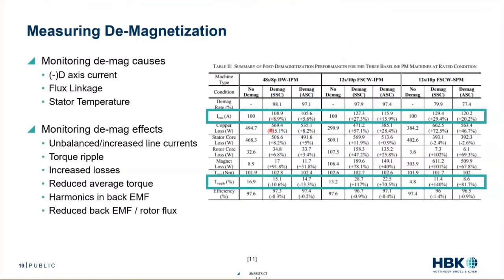I think this is a good chart and I highlighted some of the areas I think are particularly interesting. With demagnetization, we can monitor the causes. We know the causes are temperature and we know it's negative d-axis flux or d-axis currents. So we can monitor those two things — we can look at the flux linkage, we can look at the negative d-axis currents, and understand why these faults might be happening or what's leading up to these faults.